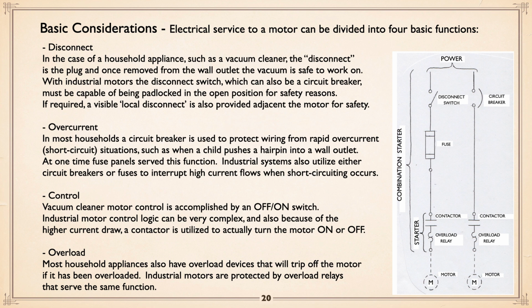Now, next one, control. On the vacuum cleaner, you've got an off-on switch. Industrial motor logic, of course, can be much more complex, but they use a contactor to turn the motor on and off. And last but not least, a lot of household appliances have overload devices that trip. If you've got an overload device on your vacuum and it gets too hot, it trips off, and you push a button. Most circuit breakers today have that ability to respond to an overload. Now, what's the difference between overcurrent and overload? Overcurrent means a massive amount of current flow. Overload means more current flow than what the motor was really designed for, and you are overloading the motor itself.